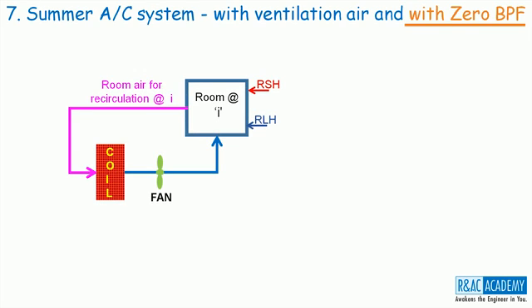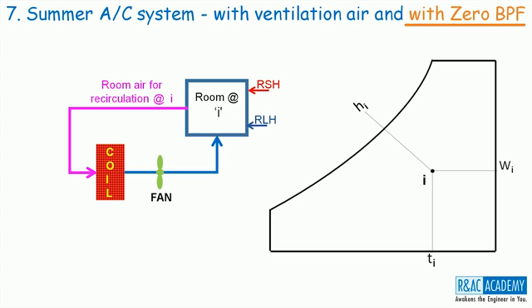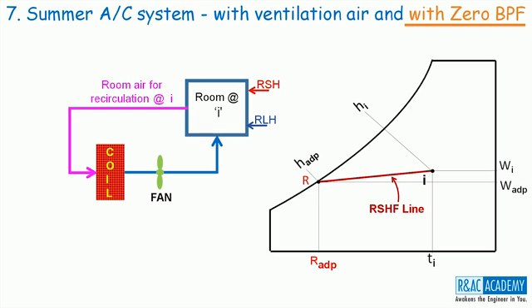Let us consider the same setup as in the previous lecture. We have a room that is required to be maintained at state I against RSH and RLH. The recirculation air comes out of the room at state I. Let us plot the state point I on the psychrometric chart. Starting from I, if we draw the RSHF line, it will intersect the saturation curve at room ADP. Up till this point, there is no change with reference to the previous case.